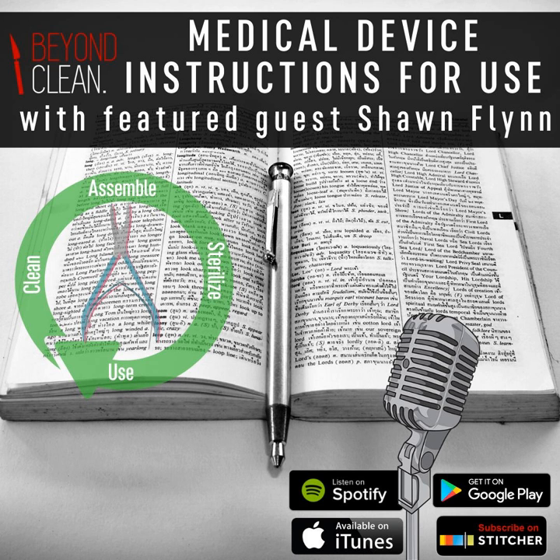First and foremost, we had to find a predicate for that. Class 2 devices allow you to look in the industry for similar things that have been cleared within the FDA under class 2. On premise, that's supposed to make it an easier process for the reviewer, as well as a quicker process for you to get your clearance, because there are existing devices out there for that.